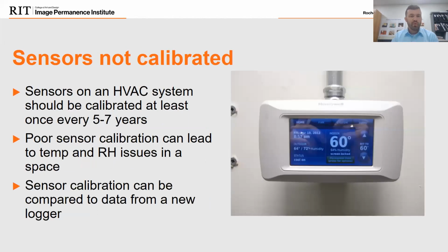And lastly, we're going to talk about sensors not being calibrated. This can be a huge fault. On an HVAC system, your sensors should be calibrated roughly every 5 to 7 years. Most sensors, even your data loggers, can go about 2 to 3 years without needing to be recalibrated. Some of the lower-end ones maybe 2 or 3 years, but decent loggers and decent sensors can give you about 3 to 5 to 7 years without needing to be recalibrated. And you really want to think about that.